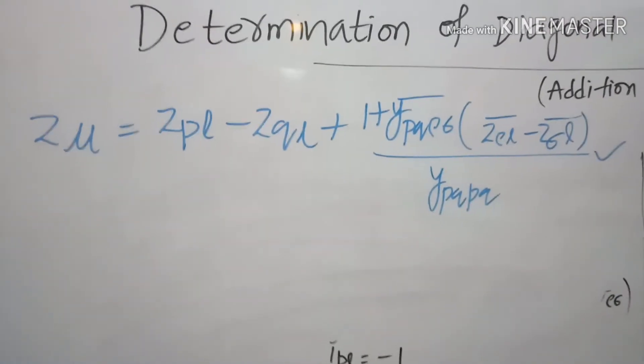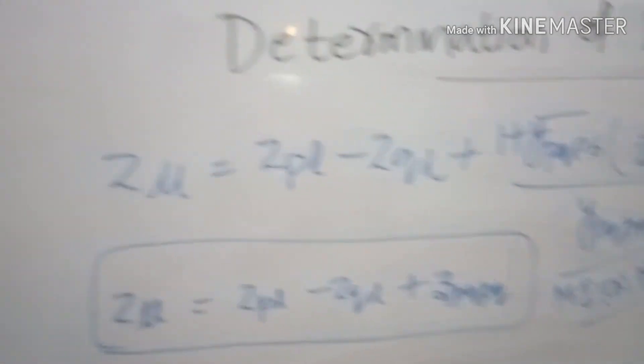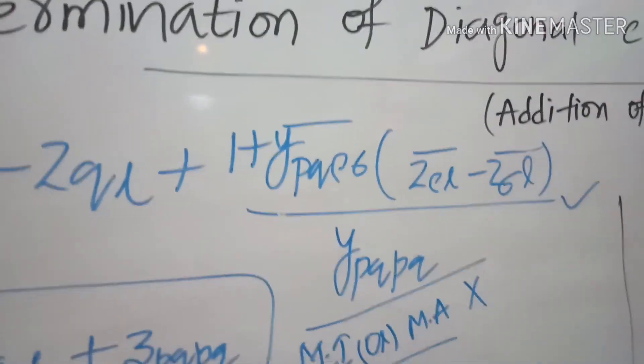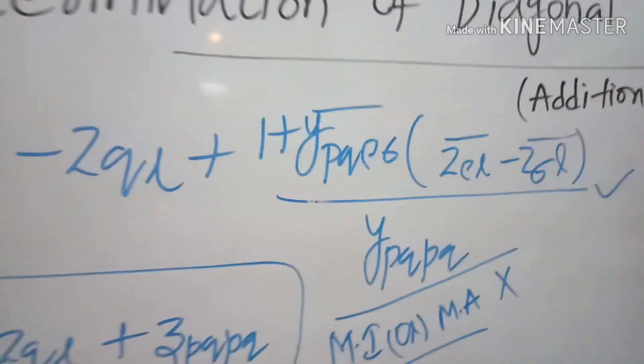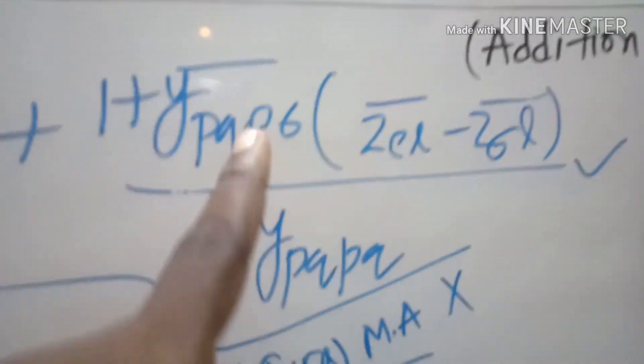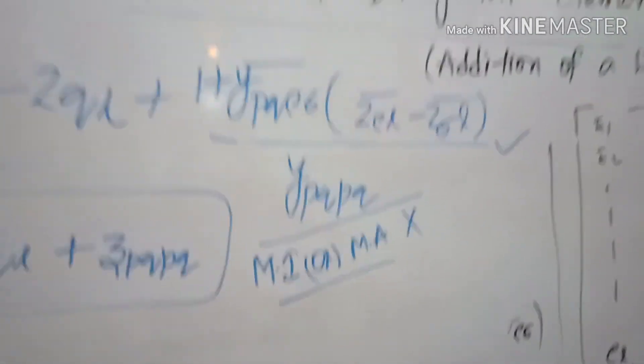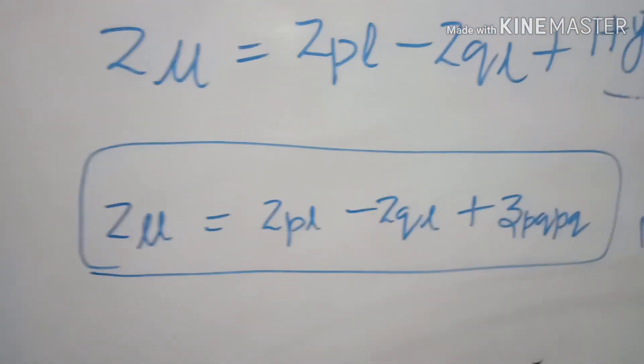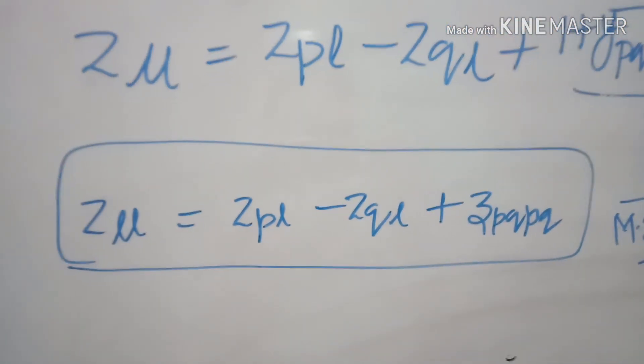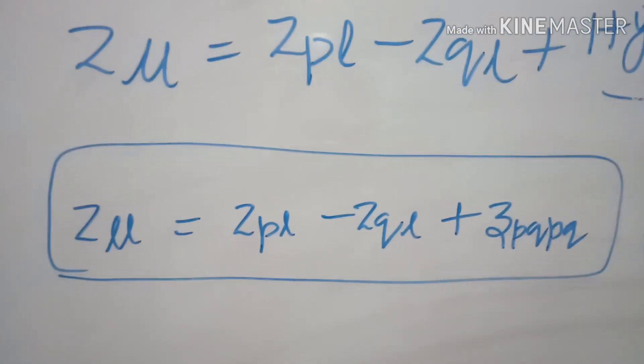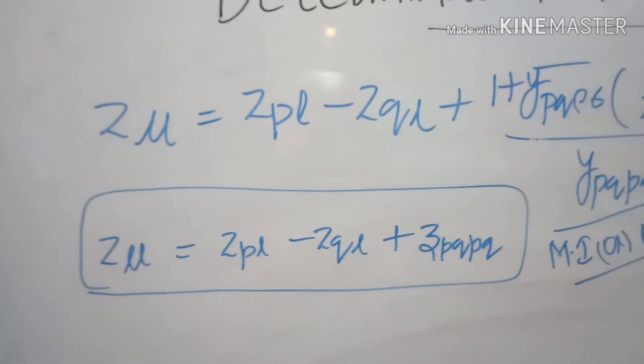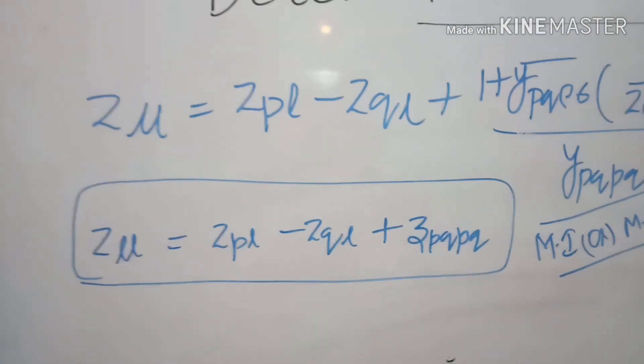Now we will see the special case: when there is no mutual impedance or mutual admittance between the added element and the remaining elements of the partial network, we can make the mutual admittance term zero. When we make this zero, we get only one divided by y_pq_pq, which is the reciprocal of self admittance — that is, self impedance. The finalized equation for the special case with no mutual impedance is: Z_ll equals Z_pl minus Z_ql plus z_pq_pq.